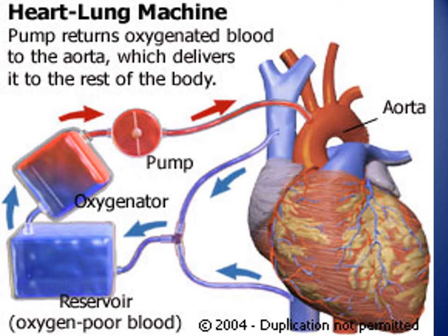This image shows a simplified heart-lung machine. Two venous cannulas from the superior vena cava and inferior vena cava collect blood to the reservoir, which is then pushed to the oxygenator, then to the aortic cannula to perfuse the body during heart surgery. The pump returns oxygenated blood to the aorta, which delivers it to the rest of the body.